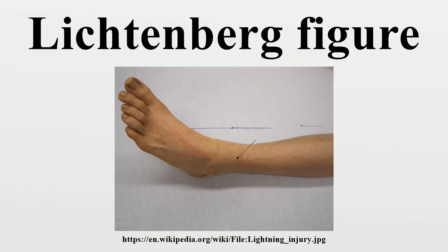Another type of 2D Lichtenberg figure can be created when an insulating surface becomes contaminated with semiconducting material. When a high voltage is applied across the surface, leakage currents may cause localized heating and progressive degradation and charring of the underlying material. Over time, branching, tree-like carbonized patterns are formed upon the surface of the insulator, called electrical trees.